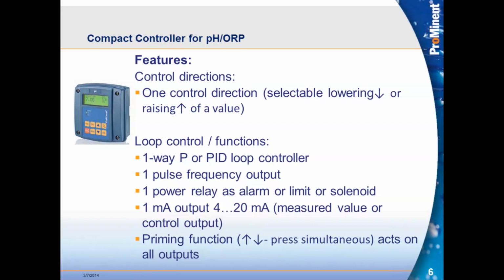Of course, it's not in ppm, it's going to be in millivolts, an ORP reading. And you can also feed bisulfite to remove the chlorine in that case. Okay, you can't do both of those from that same unit. You have to select one or the other.